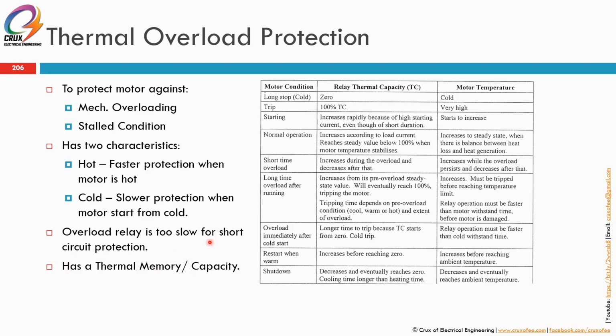For this overload relay, if you're using a bimetal, it has a thermal memory or capacity. For modern relays, you have to input correctly the cooling constant and the heating constant in the relay to emulate the thermal memory. So relay thermal capacity versus motor temperature, let's see. After a long stop, it's zero and cold. The relay will trip once it reaches 100% of its thermal capacity. Motor temperature is very high, depending on the winding temperature class, maybe class B or class F, so it can go up to 155 degrees or 180 degrees or 120 degrees. During starting, the thermal capacity increases rapidly because of the high starting current, even though for a short duration, but the motor temperature only starts to increase, not as fast.